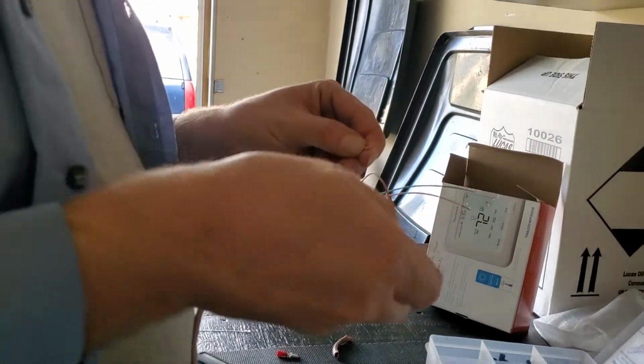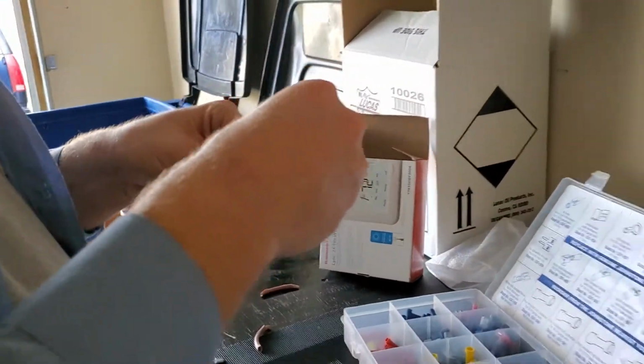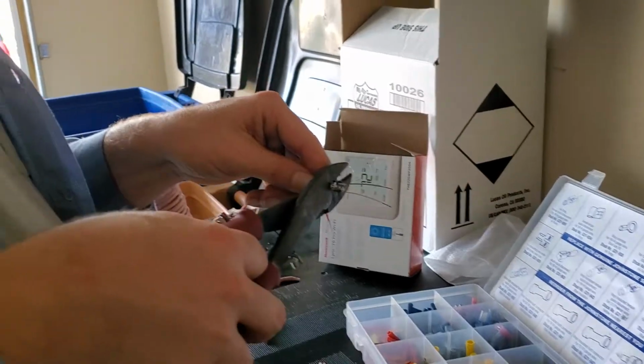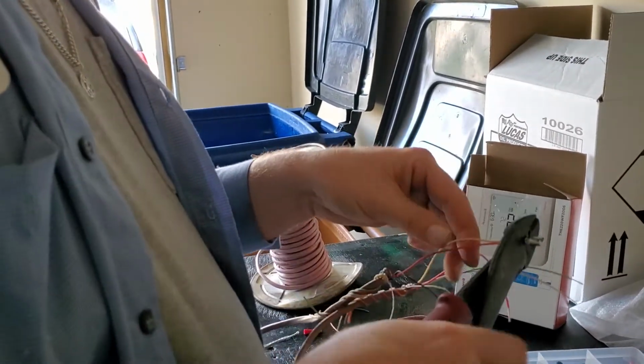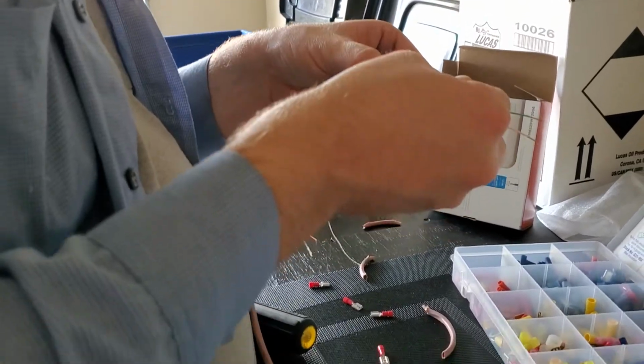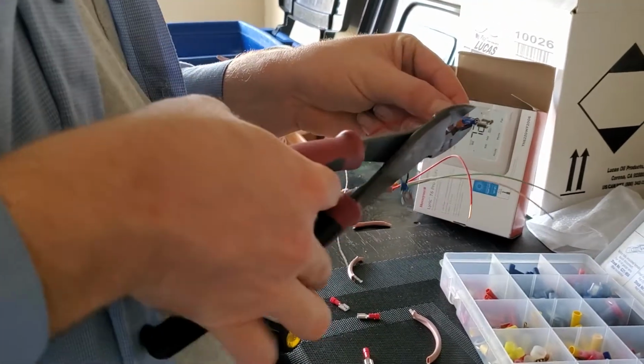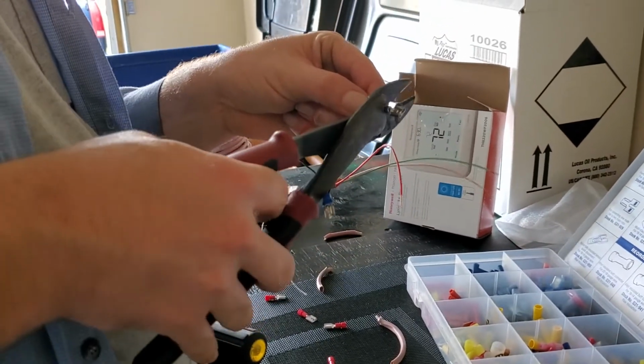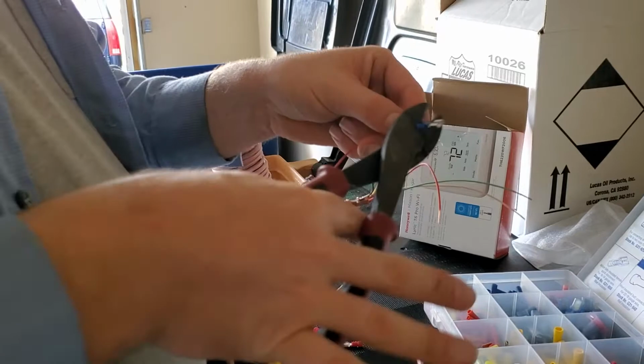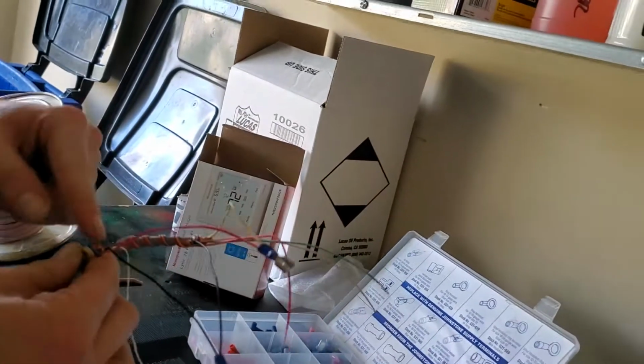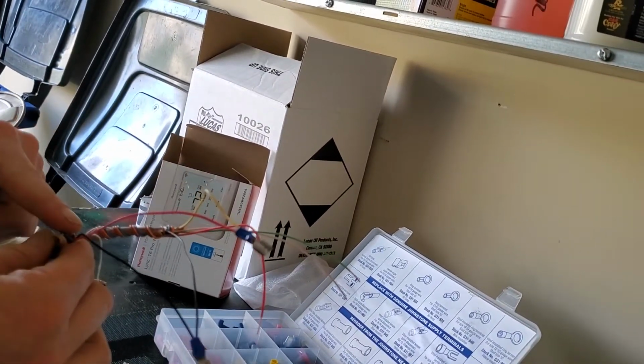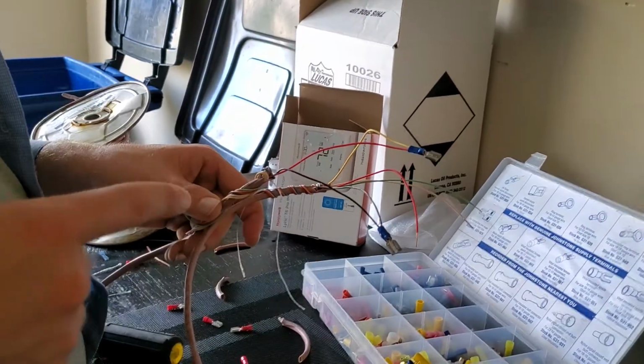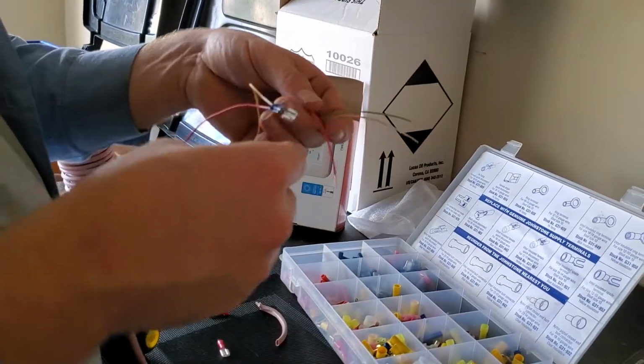Whenever you're running heat, the outside condenser's motor isn't turning - not unless it's a heat pump, that'll be a different situation. But what you would find in here is a third wire in this set, and you would take your orange wire and tie it to the other orange, just so you stay consistent if it was a heat pump. What that does is energize your reversing valve - a reversing valve allows refrigerant to flow backwards, which is what a heat pump does.